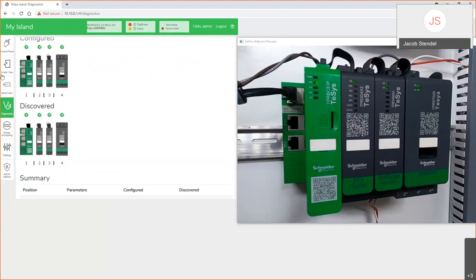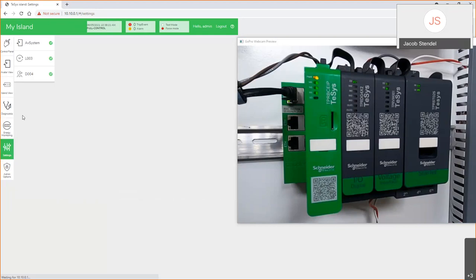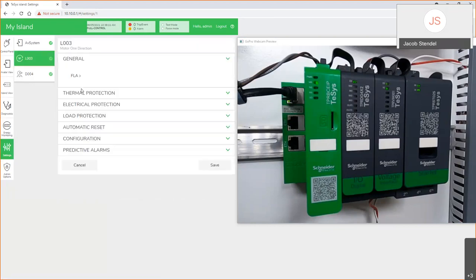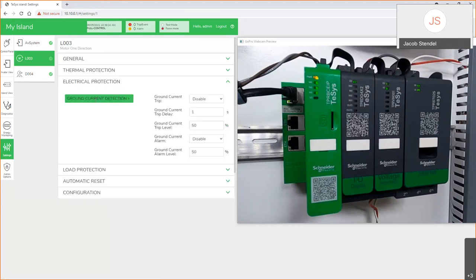So I want to go into diagnostics. Let's go into settings. I'm going to click on my avatar. And here are all the different protection modules, the protection settings you can configure on just the one starter. I have my FLA configured at 0.9. You can have your ground current. That's a big deal if, perhaps, you've got a phase that's leaking out, your bearings are failing, something's causing issues, you can set that here.